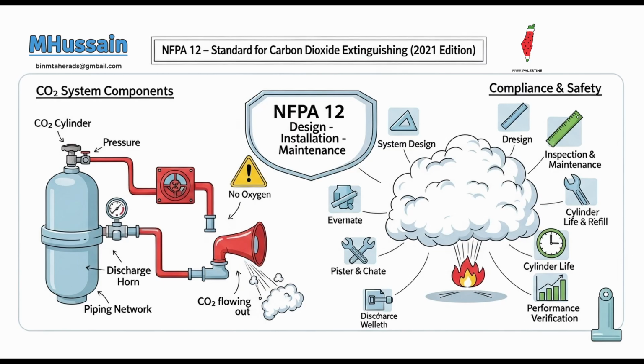Right. This calculation assumes that CO2 expands to approximately 9 cubic feet per pound, 0.56 cubic meters per kilogram. Without adequate venting, the pressure could not only damage the enclosure but also hinder the uniform distribution of the extinguishing agent, leading to an ineffective suppression. So venting is crucial for the room and for the system to work. Absolutely critical. Local application systems, chapter 6.